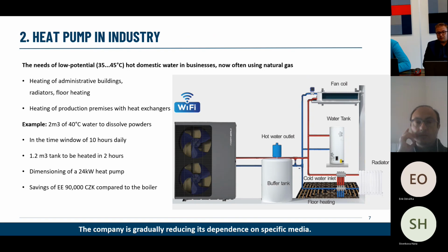So we calculated what it would take to actually size a heat pump. This requirement to heat up that water tank in 2 hours is quite aggressive. You would probably be okay doubling that time and still be able to perform the operations, but they plan to expand, so we said, let's leave you with a contingency at the end of this project.